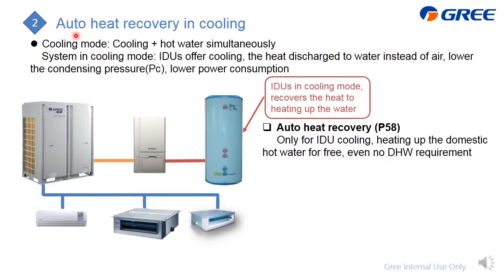Next is Auto heat recovery. And first of all, what does this mean? That means it is only in cooling mode, but at the same time it can produce the domestic hot water. And here is how it works, and you can find that if this indoor unit produces or requires cooling, just like this, we need to release heat, either in the outdoor unit, but we can transfer this heat to here. Even if you don't require the domestic hot water, we can still produce it. And for this one, you can get the free hot water.